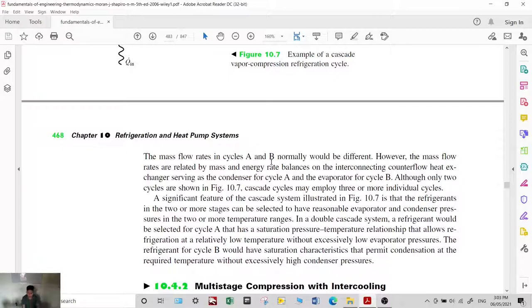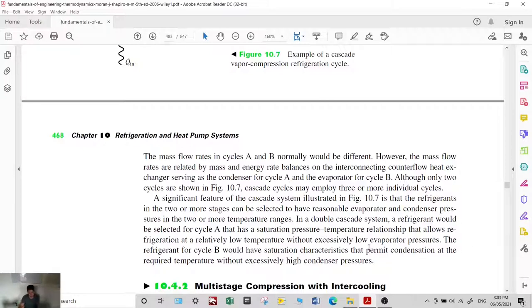A significant feature of the cascade system is that the refrigerant in two or more stages can be selected to have reasonable evaporator and condenser pressures. In the double cascade system, a refrigerant is selected for cycle A that has a saturation pressure-temperature relationship allowing refrigeration at relatively low temperatures without excessively low evaporator pressures.